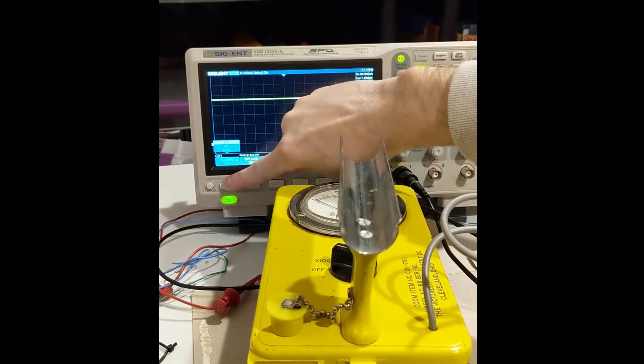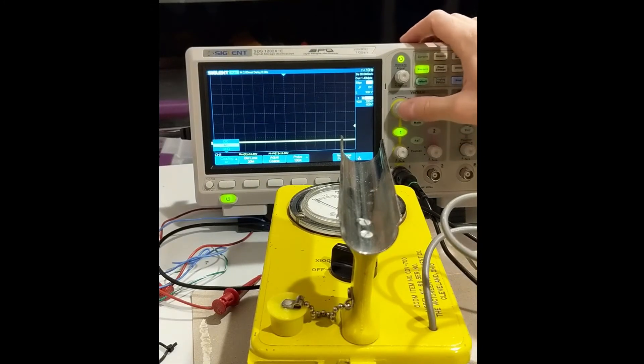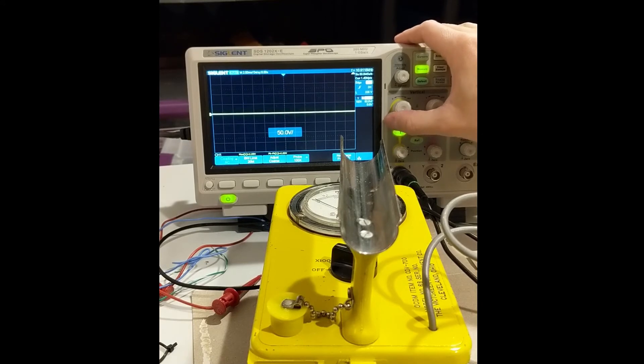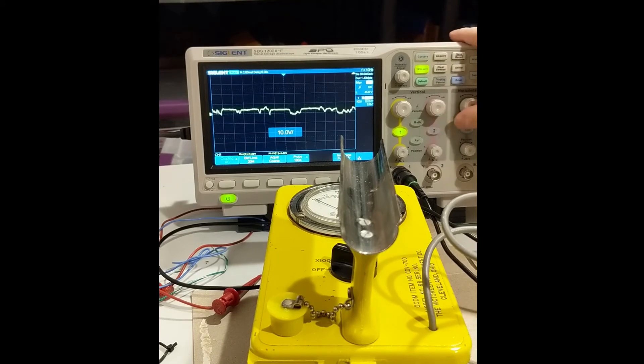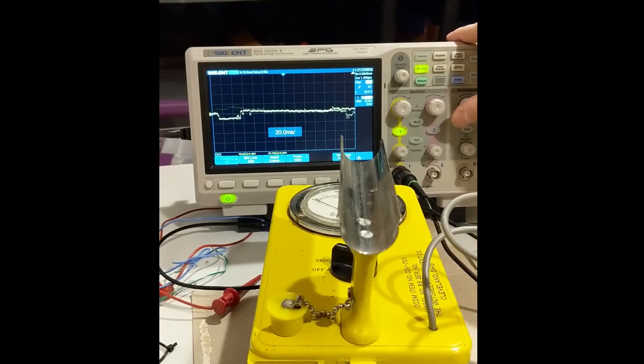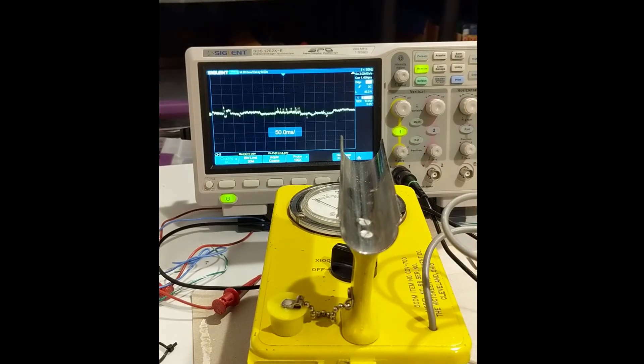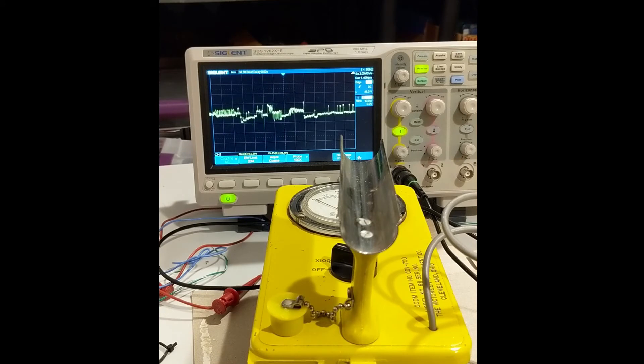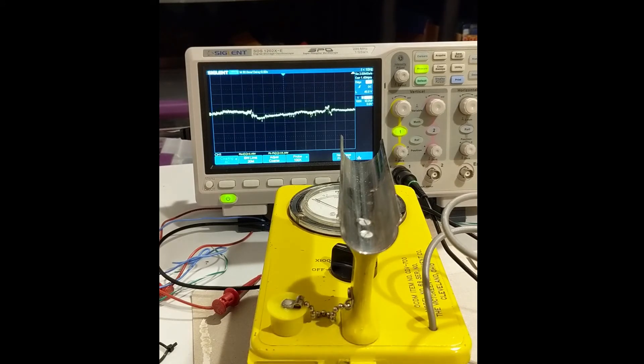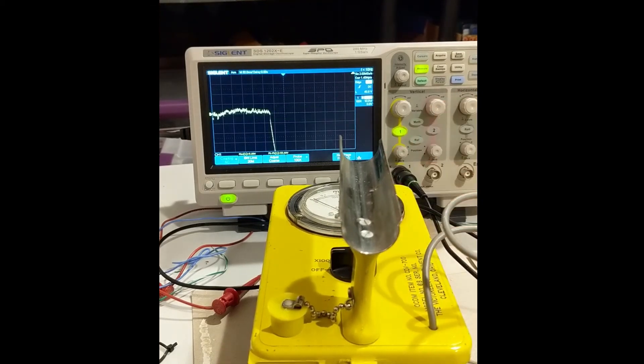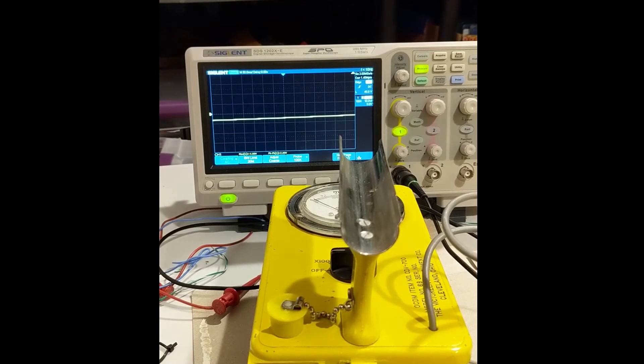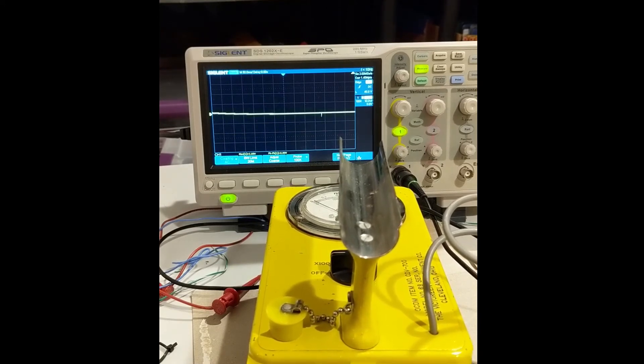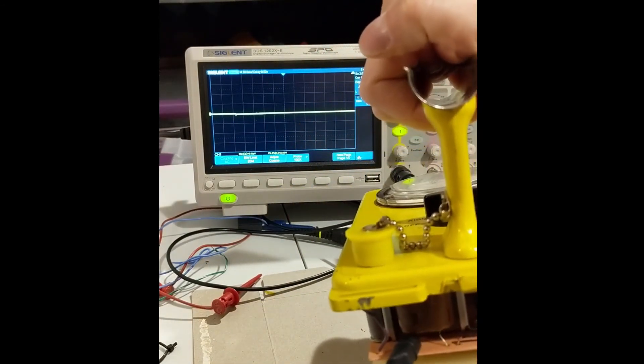So it's not the most regulated thing in the world, but it's good enough that the pulse detection circuit does not sense this garbage. And it looks like we're reading about 20 volts peak to peak, and that's on approximately a 920 volt output. It's adequate enough for this type of a meter and this type of a circuit. So there we go, we tested it, we verified it's working, and now we can finish putting it back together.